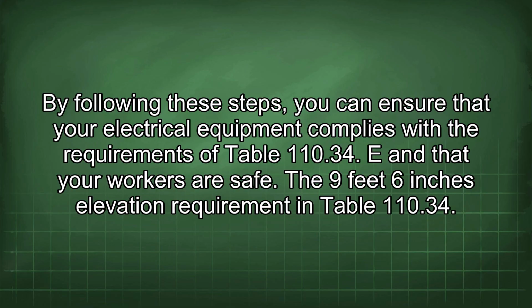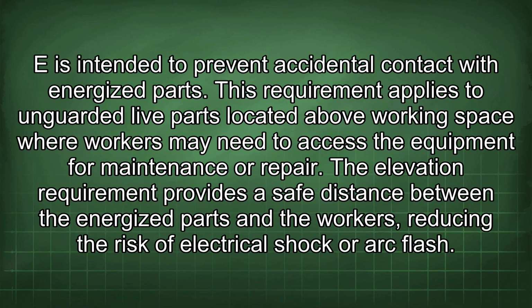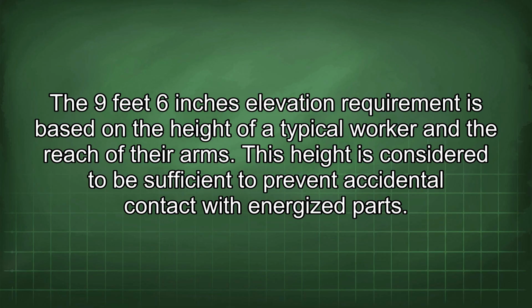The 9 feet 6 inches elevation requirement in Table 110.34 is intended to prevent accidental contact with energized parts. This requirement applies to unguarded live parts located above working space where workers may need to access the equipment for maintenance or repair. The elevation requirement provides a safe distance between the energized parts and the workers, reducing the risk of electrical shock or arc flash. The 9 feet 6 inches elevation requirement is based on the height of a typical worker and the reach of their arms. This height is considered to be sufficient to prevent accidental contact with energized parts.